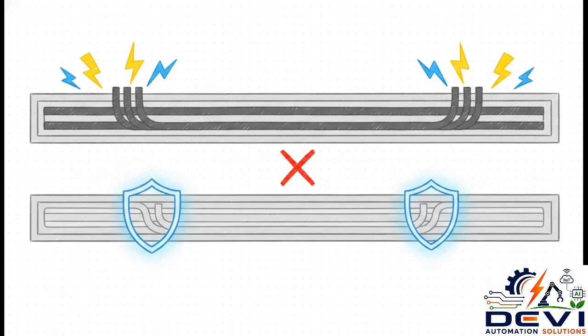Okay, when it comes to cable routing, there is a golden rule you have to follow. You have power cables handling high voltage and high current. Then you have control cables handling highly sensitive, low voltage signals. The rule is simple: always route them separately. If you run your power and control cables in the exact same cable tray, the electromagnetic interference from the power lines will induce noise into the control lines, and that causes absolute chaos in your system. And remember, those control cables must always be shielded, no exceptions.